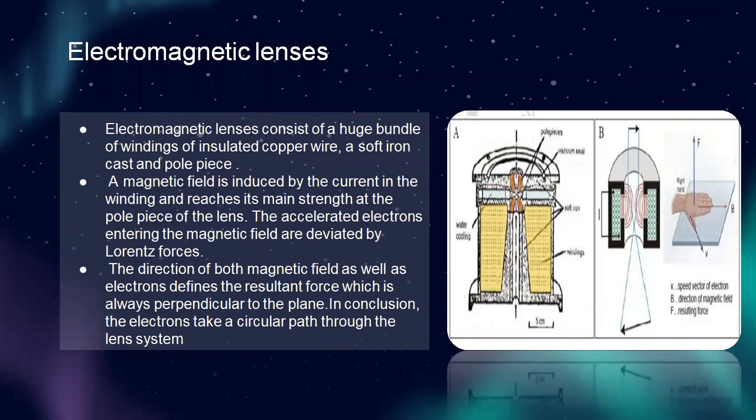Next, electromagnetic lenses: electromagnetic lenses consist of a large bundle of windings of insulated copper wire, a soft iron core and pole piece. A magnetic field is induced by the current in the windings and reaches its main strength at the pole piece of the lens. The accelerated electrons entering the magnetic field are deviated by Lorentz forces. The direction of both magnetic field and electrons defines a force which is always perpendicular to the plane. In conclusion, the electrons take a circular path through the lens system.